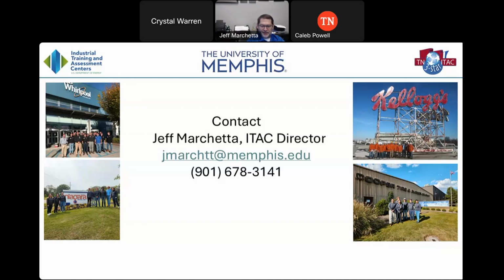Sure, good question. It depends on the application of the VFD, but if we go specifically to the HVAC systems, we use climate data, which gives us an assessment of the variation in outdoor climate conditions. We look at typical set points inside the plant. Based on those, there is a published set of ASHRAE loading estimates that we use for HVAC equipment. So when we look at a system that's start and stop, you're basically looking at 100% load, although you can look at when it stopped and average that in as well.